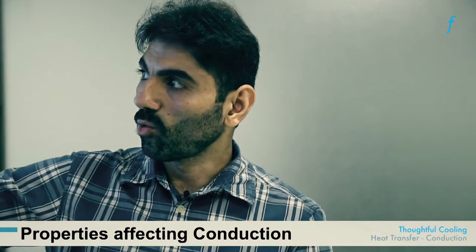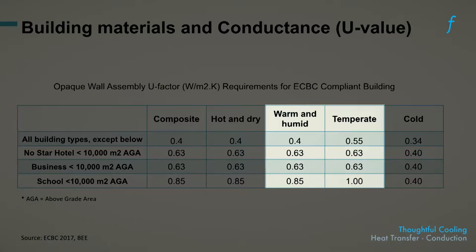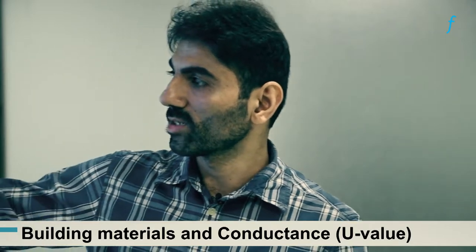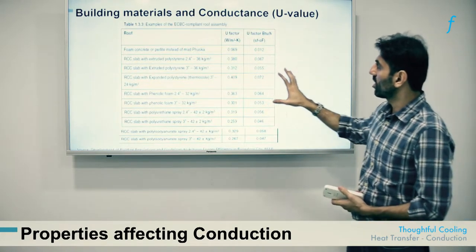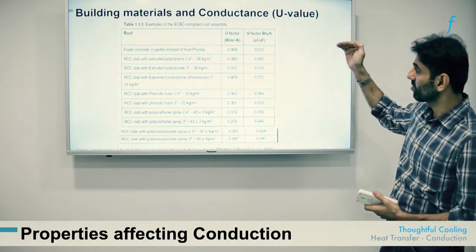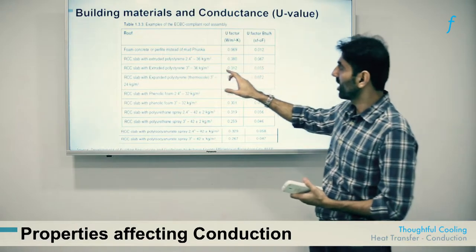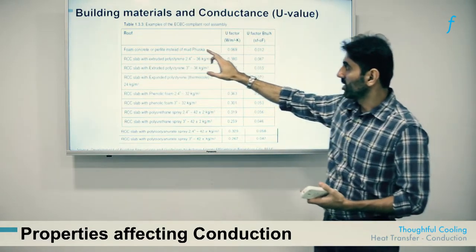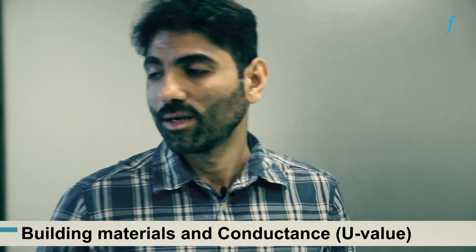This implies that almost no ECBC-compliant building can avoid insulation — simple building materials such as brick and concrete without insulation will not give a U value low enough to meet ECBC compliance. For a warm and humid climatic condition, the U values required are lower than for a temperate zone, because the threat of heat ingress is much higher. U values required for an ECBC-compliant roof assembly are also much lower than those of simple materials like brick and concrete, making insulation almost imperative in modern buildings.